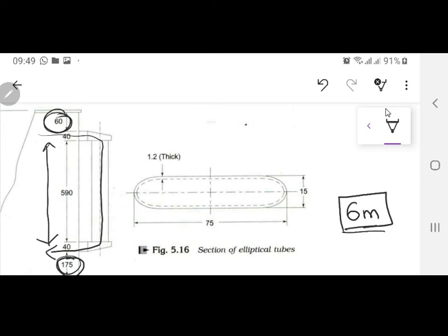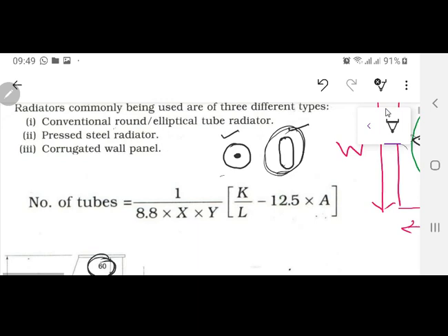कितनी tubes लगानी है, this has to be decided by your total wastage of power which is going to be dissipated. Now what is that total wastage of power? That total wastage of power is the no load losses plus the I square R full load losses over there. And how you are going to find out that number of tubes? The formula is there in this one.